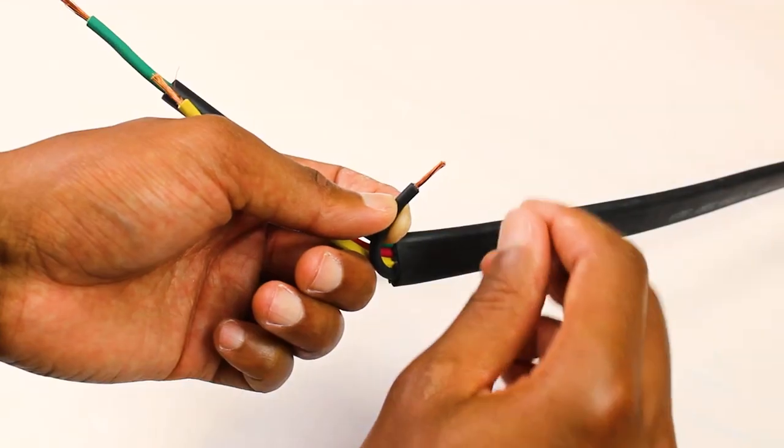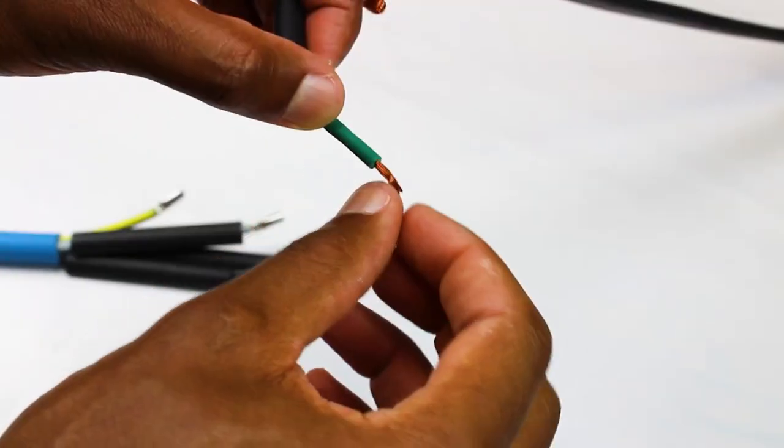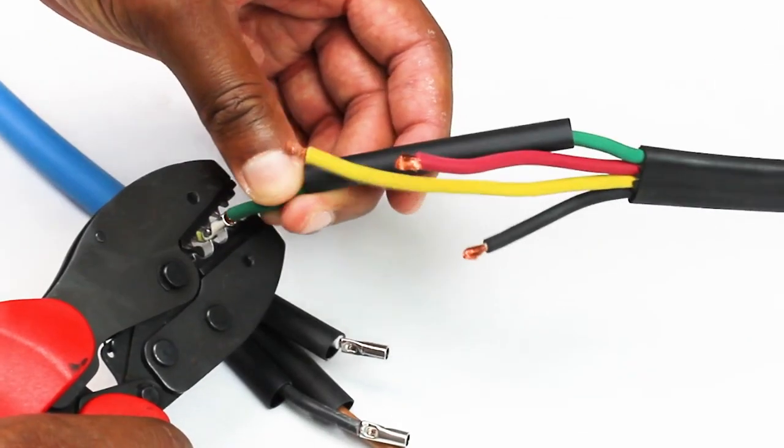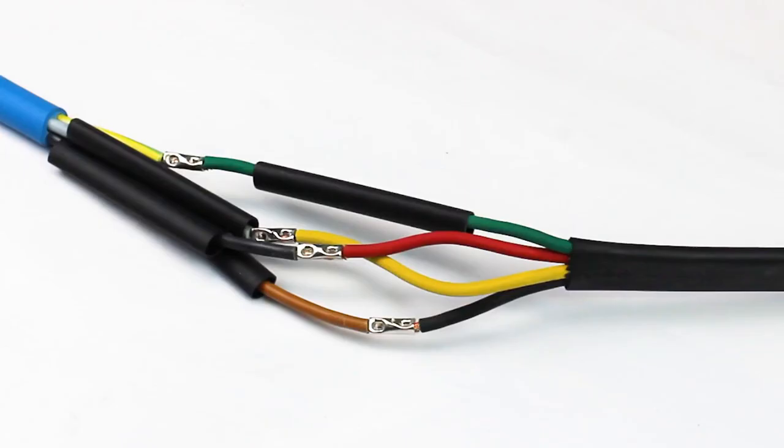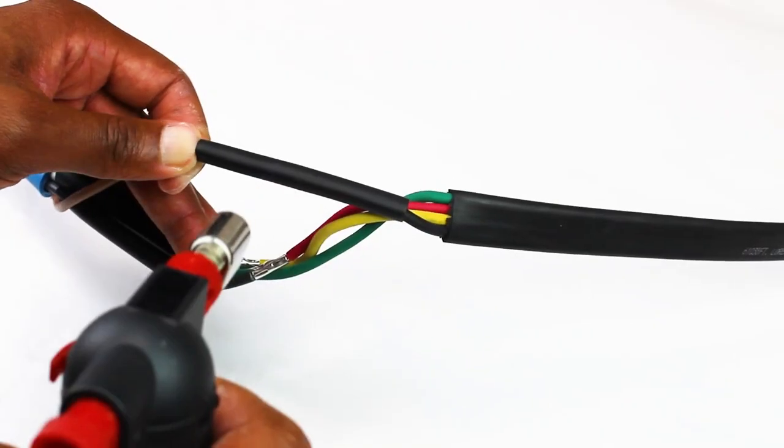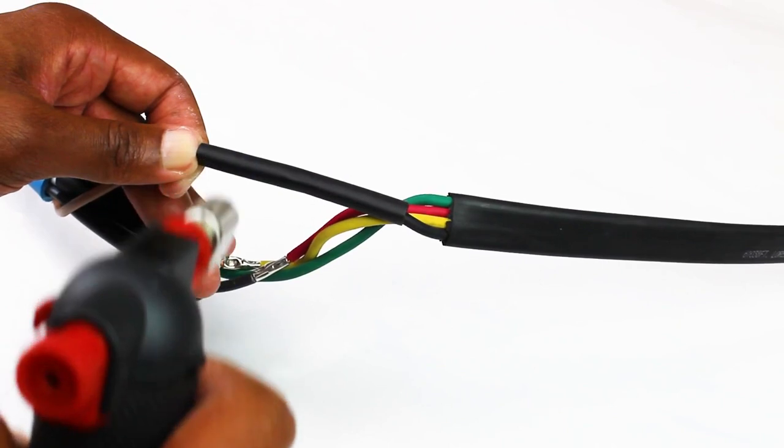It might be necessary to double the wire ends of 2.5 mm² motor cables. When heating the shrinking tubes, start from the middle and move slowly toward one end.